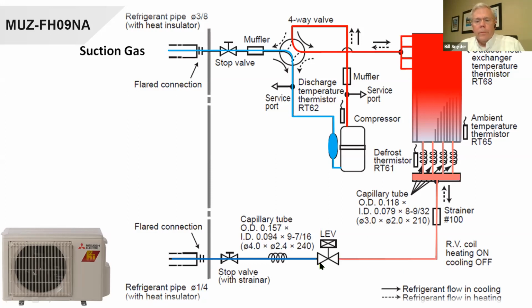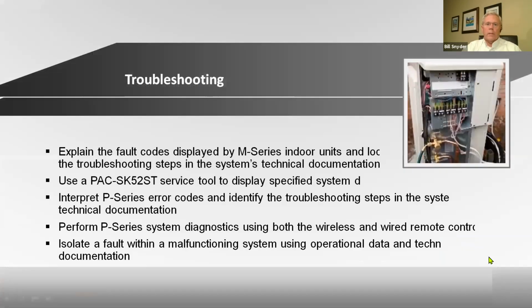We go through another strainer, another linear expansion valve, another cap tube, and then through the valve to the indoor equipment, and then back through a muffler, a reversing valve, service port, suction line accumulator, and back to the compressor. This is relatively simple, but I wanted to show you how we have all these cap tubes and all these strainers. The strainer can plug up, the cap tubes can plug up, the LEVs can plug up. So again, really good installation practices mean a great deal on this.